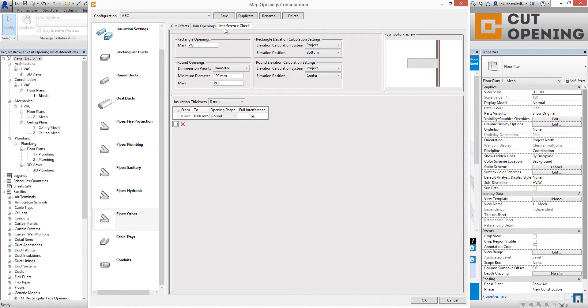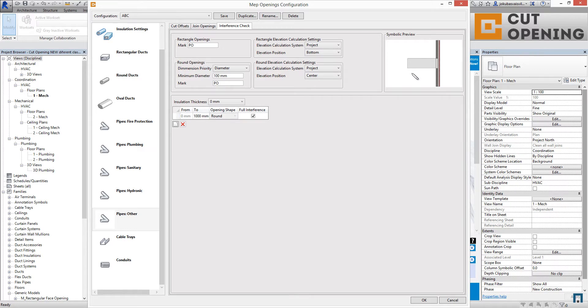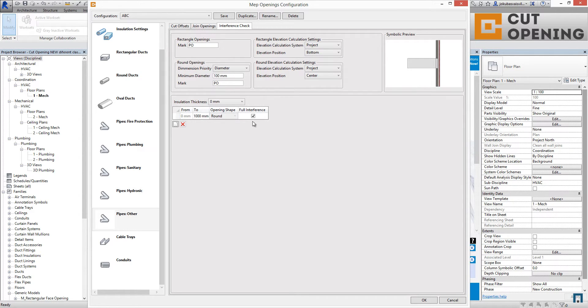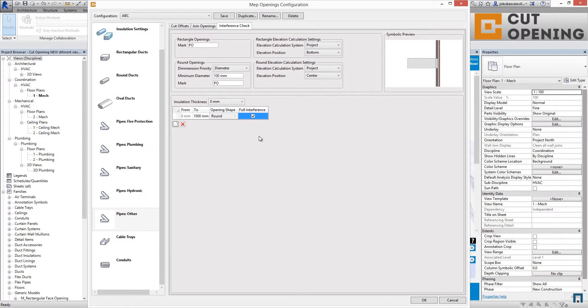The last configuration is interference check. This means that if you want to cut openings even when the MEP object does not fully cross the wall or ceiling, you need to uncheck this checkbox. If you don't want to cut openings in such situations, you need to check this checkbox so that full interference is required. Again, we have the same size ranges here, and you can apply the same steps for all insulation thicknesses in your project.